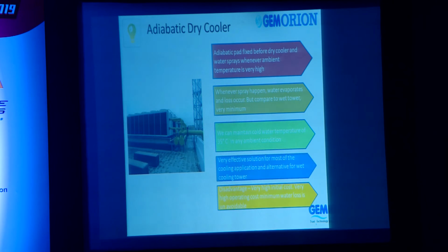Here we adopt the same dry cooler technology, but in front of the dry cooler we have some pads and use some quantity of water. This consumes water, but it will be about 25 to 30% of the conventional cooling tower water, so it saves around 70% water. But it has the disadvantage that it is very power intensive, and capital-wise it is very expensive. This is one of the solutions we can adopt for conserving water. When the ambient temperature is lower, the tower works in dry mode, and when the ambient temperature goes up, we can get the adiabatic mode. But again, around 33 to 34 degrees is the temperature we can get. So most molding applications, power packs, these cases can be adopted.